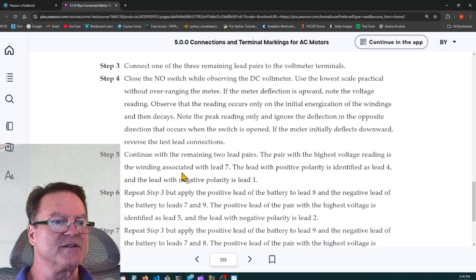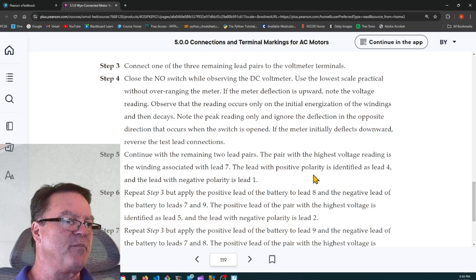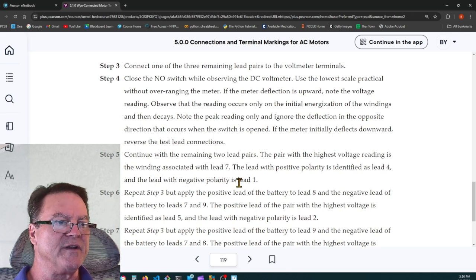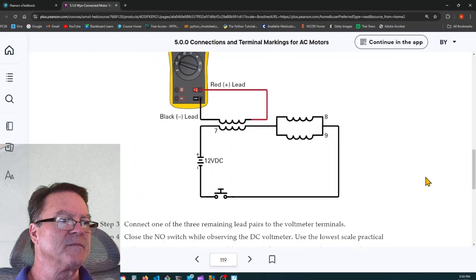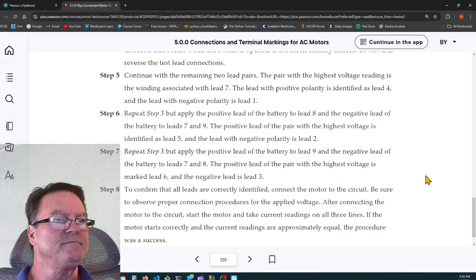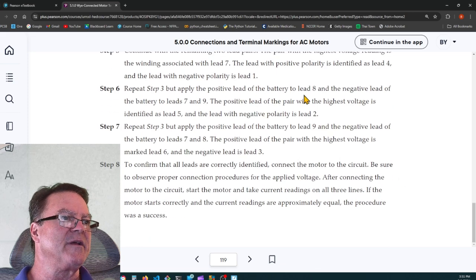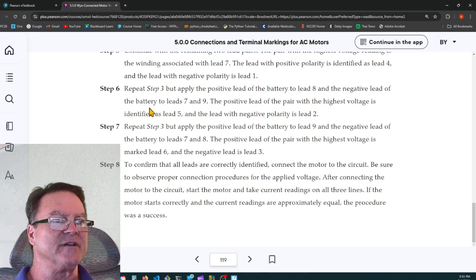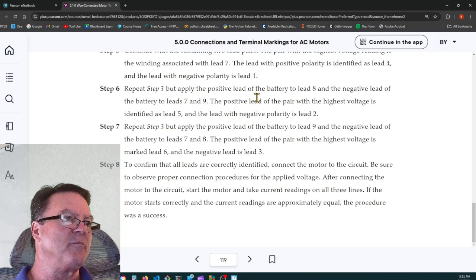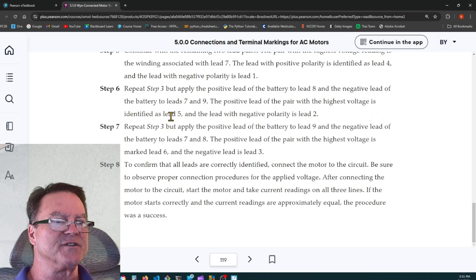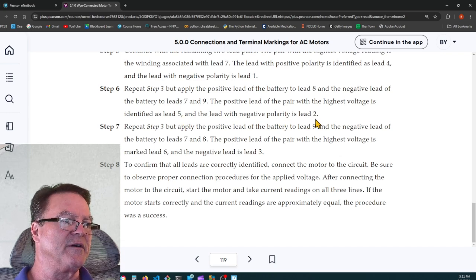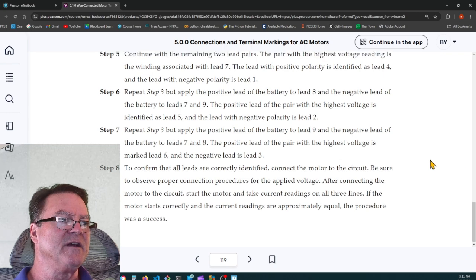The pair with the highest voltage reading is the winding associated with lead 7. The lead with a positive polarity is identified as lead 4, and the lead with a negative polarity is lead 1. Repeat step 3, but apply the positive lead of the battery to lead 8 and the negative lead of the battery to leads 7 and 9. The positive lead of the pair with the highest voltage is identified as lead 5, and the lead with the negative polarity is lead 2. Repeat step 3, but apply the positive lead of the battery to lead 9, and the negative lead of the battery to leads 7 and 8. The positive lead of the pair with the highest voltage is marked lead 6, and the negative lead is lead 3.